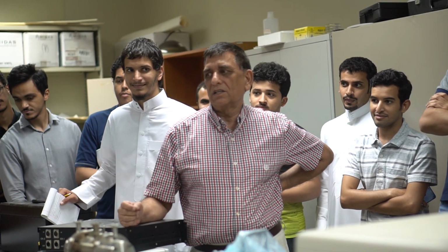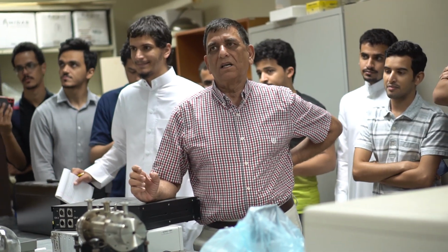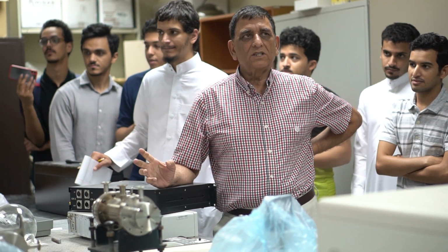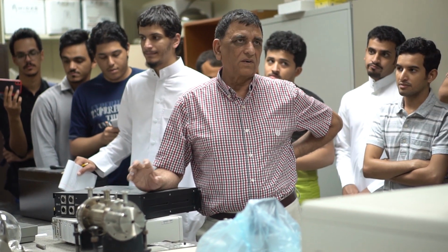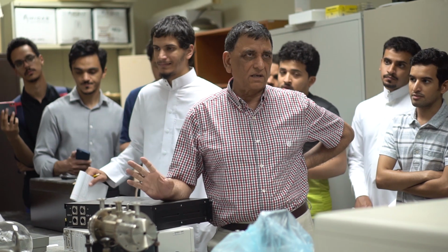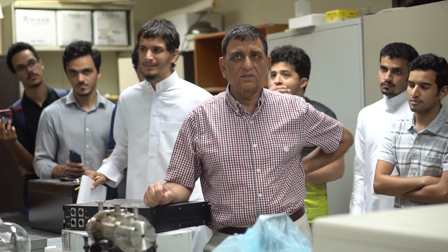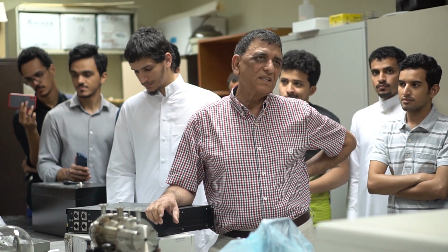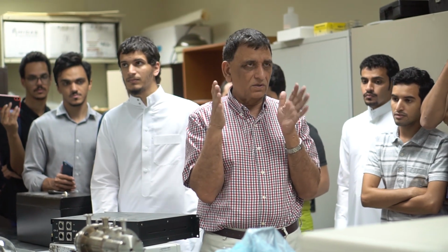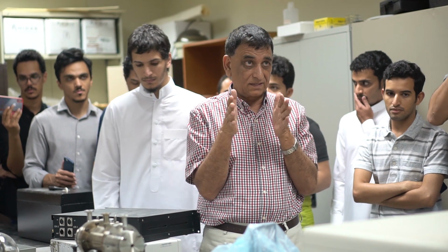This excimer laser is basically built on the principle that we mix argon and fluorine gas. Fluorine as F2 is a stable gas, it doesn't need any electron. Argon also doesn't need an electron. But when we put these two gases in a high electrical discharge, we have two electrodes and apply a very short nanosecond pulse on these electrodes, around 28 kilovolts.